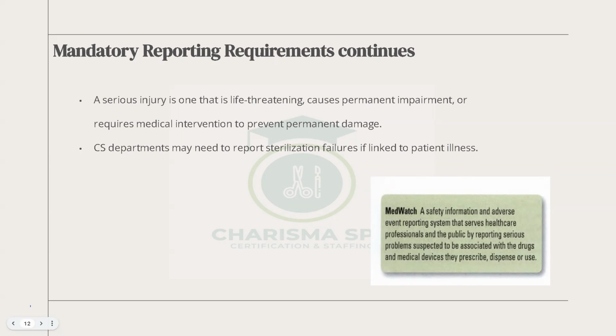reported quickly. The CSPD or CS department may need to report sterilization failures if linked to patient illness. So if the biologicals that we are using, which is classified as class 1, biological is classified as class 1.